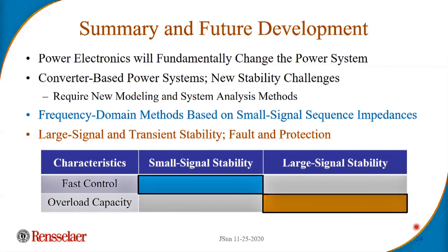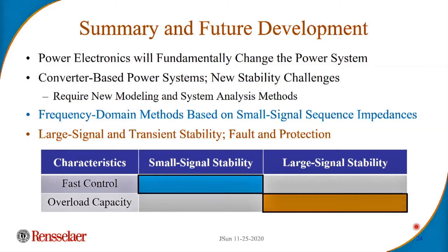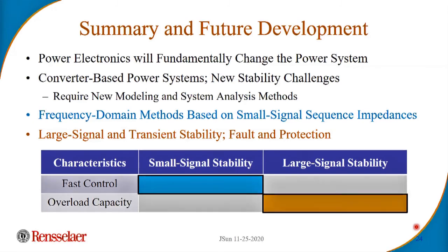Dylan, I'm going to reflect on that comment just for Luke, because I've recently done some engagement with a company that was trying to model inverters in a solar farm. They were power system people, and were convinced of the validity of independent harmonic models with current sources. All they had to do was figure out the harmonic impedances by measurement. We had a fairly robust discussion where I pointed out that as soon as you start to produce nonlinear loads, there are practical effects like dead times, and the fact that in the end it's a voltage source inverter, that didn't show up in the control loop analysis and were extremely difficult to model in an effective way.